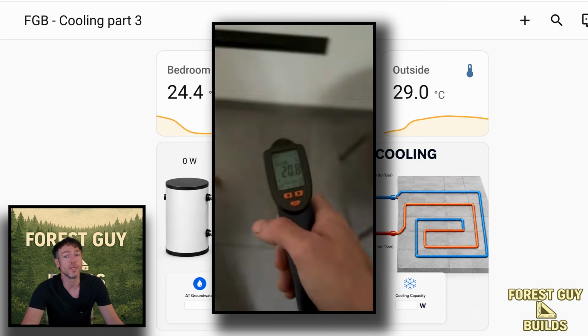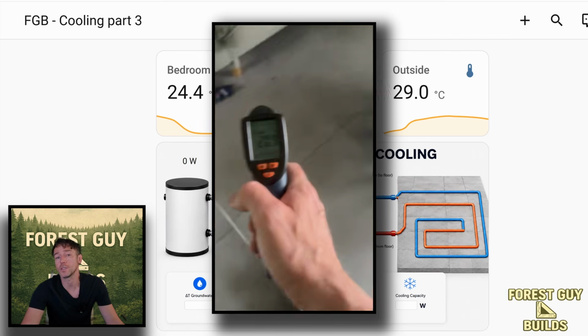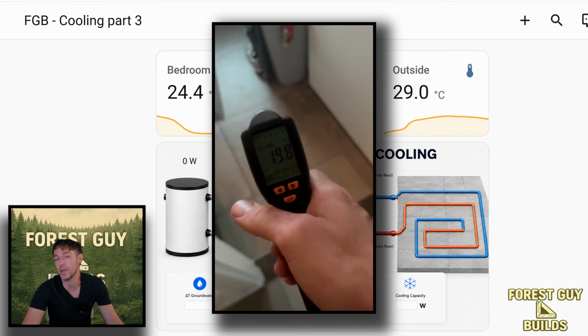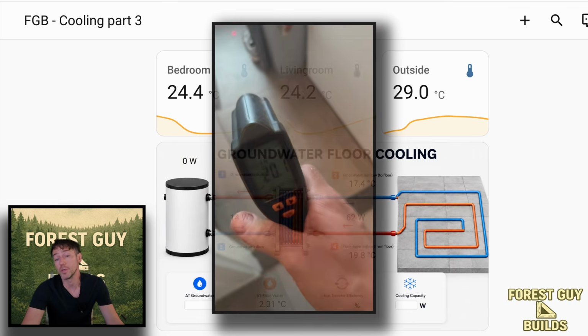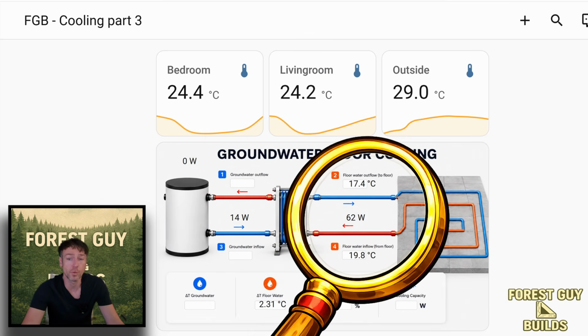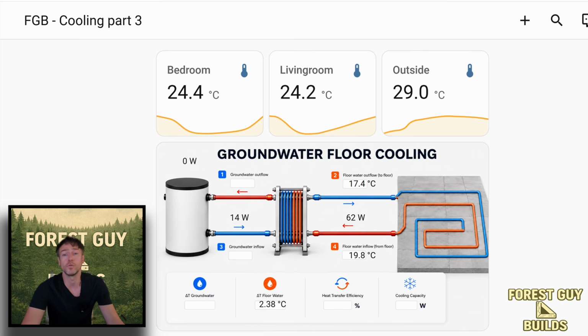I measured the floor today and it was about 20, 21 degrees. On some places where there's a smaller loop in the floor, it was about 19.5. That we see this change between the inflow and the outflow means the floor is still absorbing heat from the house and transferring it back into the water.